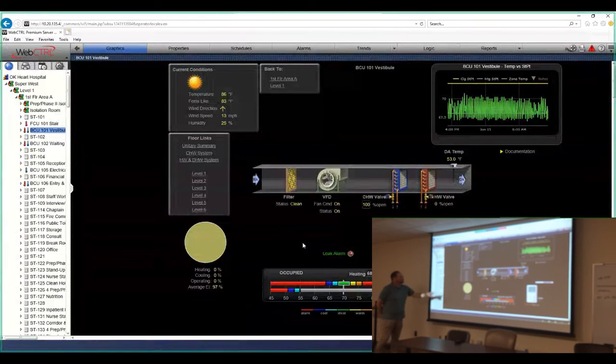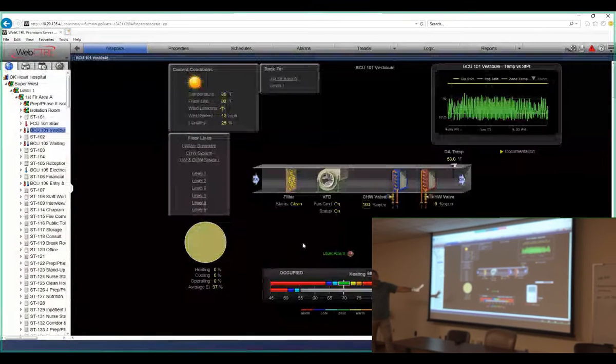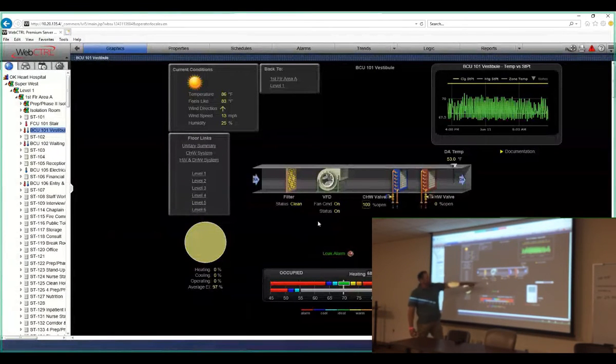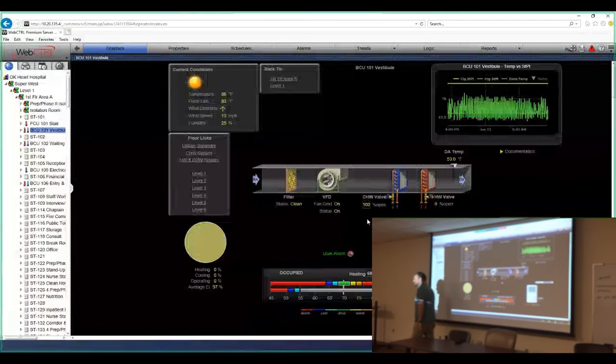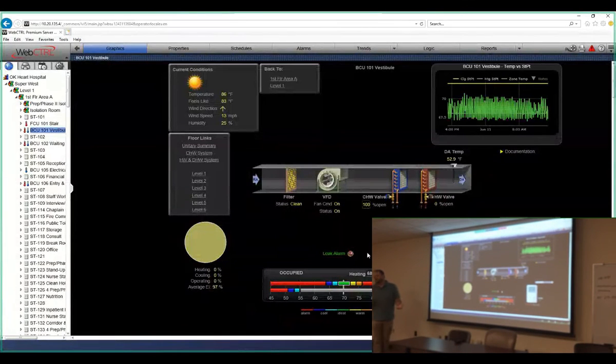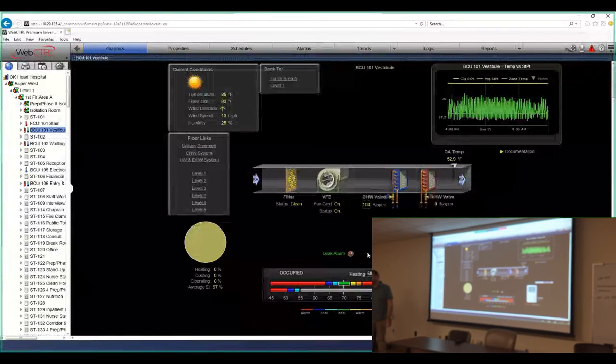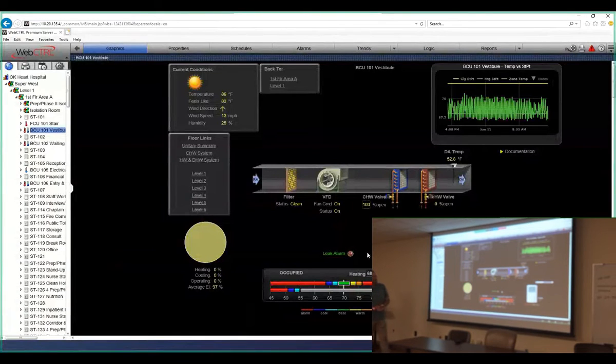Right now, the TAB guys are working in the building. That's why you probably got a lot of alarms too. Look, the chill water valve's open. We're getting a discharge temperature of 53 degrees. They're working on finalizing and testing some things on the chill water side of the water valve. So I'm assuming that's why it's open.